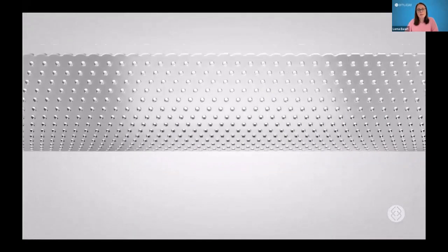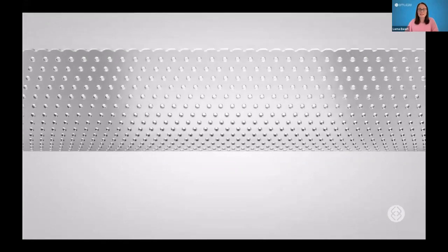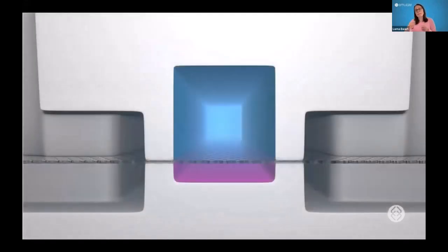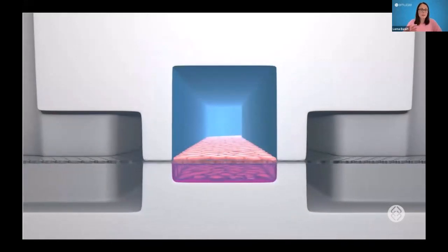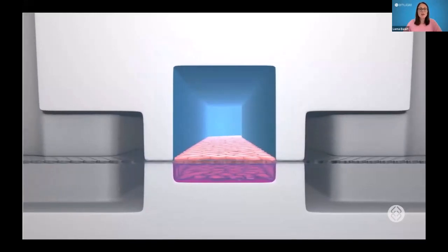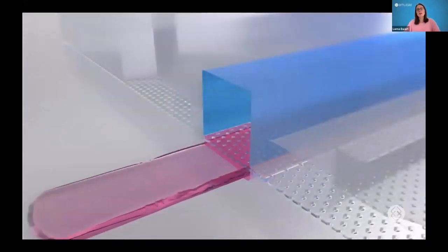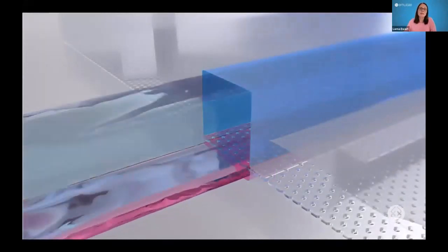As I mentioned before as well, these channels are separated by a porous membrane. The pores here are 7 microns in diameter. This membrane is then coated with an extracellular matrix specific to the cells that we want to seed. So typically we put an epithelial cell on top and an endothelial cell on the bottom. Unique to our platform is the ability to apply a mechanical stretch, which you saw there with the vacuum channels.